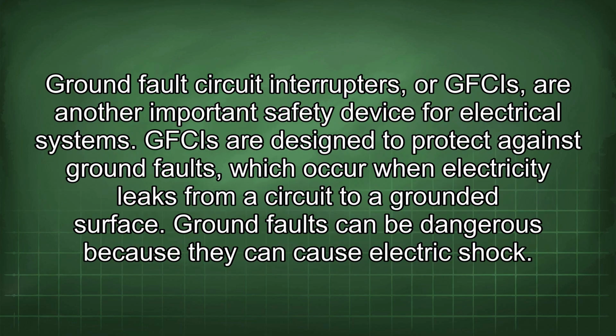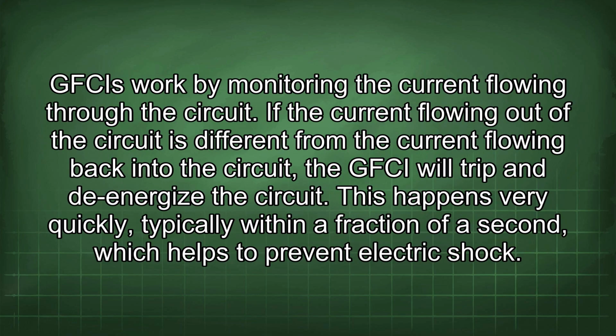Ground fault circuit interrupters, or GFCIs, are another important safety device for electrical systems. GFCIs are designed to protect against ground faults, which occur when electricity leaks from a circuit to a grounded surface. Ground faults can be dangerous because they can cause electric shock. GFCIs work by monitoring the current flowing through the circuit. If the current flowing out of the circuit is different from the current flowing back into the circuit, the GFCI will trip and de-energize the circuit. This happens very quickly, typically within a fraction of a second, which helps to prevent electric shock.